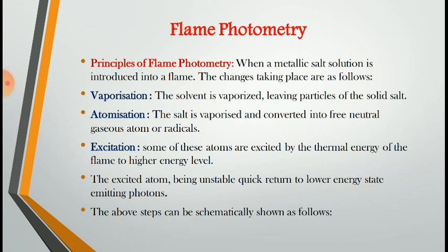Actually, there are three major steps in the basic principle of flame photometry. The first step is vaporization, the second is atomization, and the third is excitation. First we will see vaporization. In this, the solvent is vaporized, leaving particles of the solid salt.